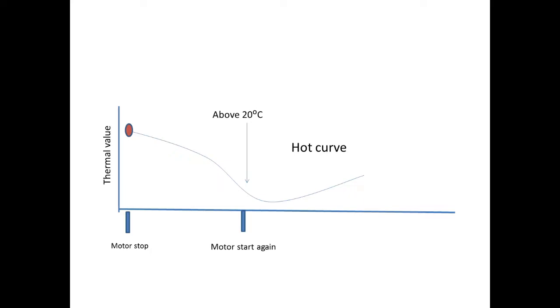Also, if the motor has been stopped for some time or a long time, and the relay has still not reached the cold area — that is if it is below 20 degrees but above 10 degrees Celsius — even in that area, if you start the motor, your relay will consider it a hot curve. By this I think you can clearly understand what is cold curve and what is hot curve. The cold curve is simply when you start the motor initially. The hot curve is when you restart the motor again within a shorter time gap.